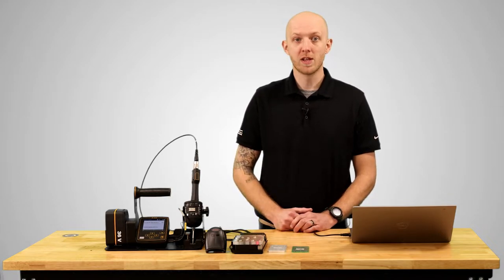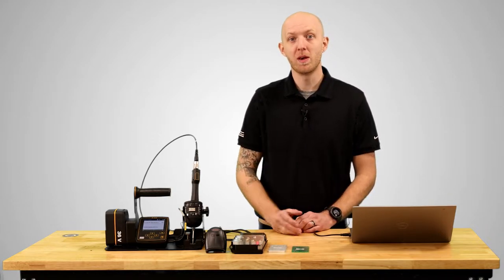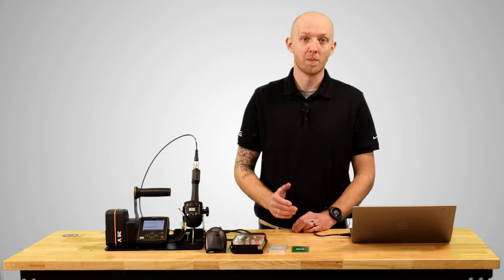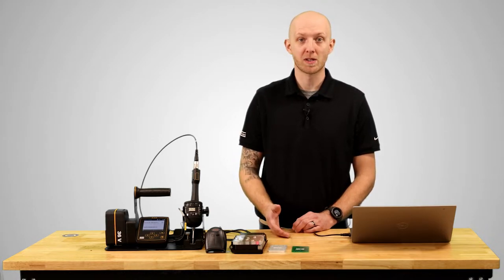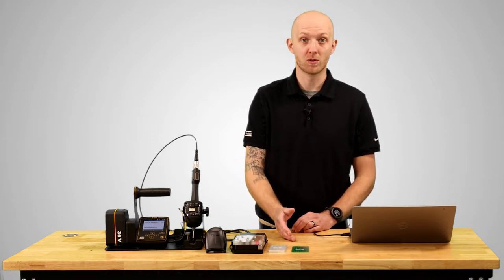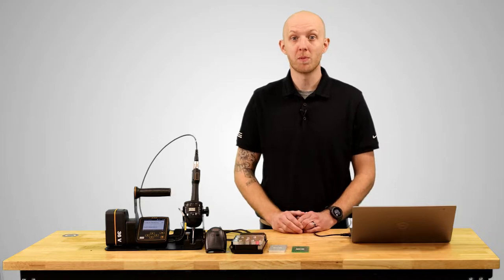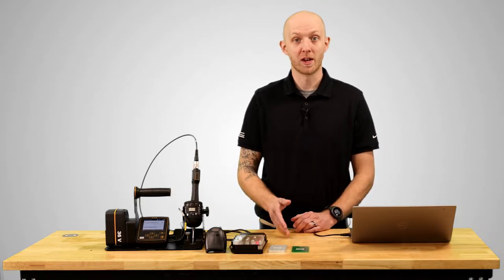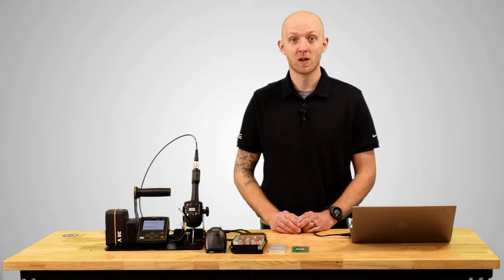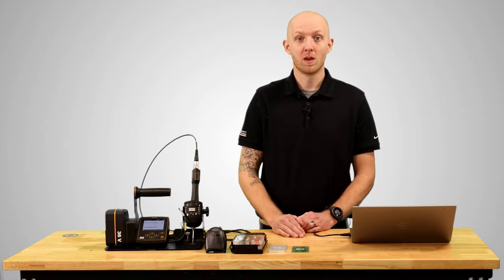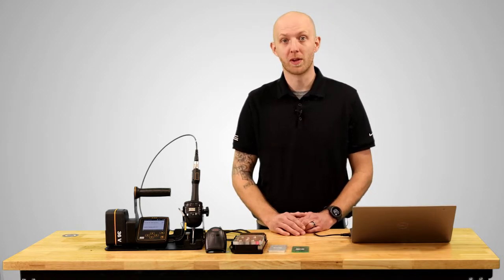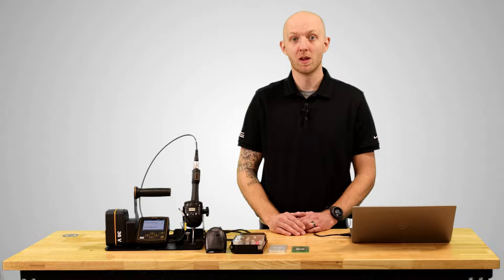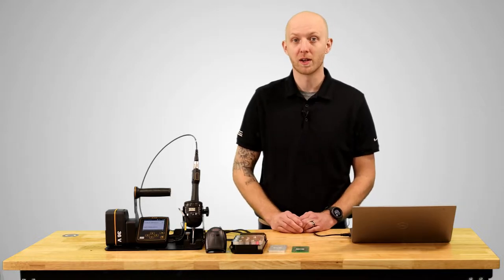For example, this PCB board in front of me has six screws. In a batch sequence, I can select a specified tightening program for these six screws and the system will not let me move on to the next batch until it has received six okay signals from the tightening. This ensures that all six screws were placed in the board and tightened correctly before the operator can move on to the next part.